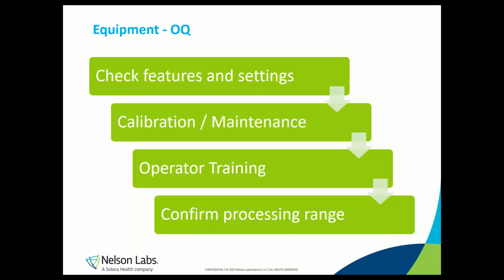The final key point is to determine the acceptable range of sealing for the specific package or the intended processing window. This is usually done by starting with a recommended setting and going up or down from there to see how that affects the seal. This is done either by performing peel testing on each setting to get the seal strength value or evaluating the visual appearance of the seal. You then pick a high, a nominal, and a low based on the seal strengths and or visual aesthetics. You can also just take the pouch manufacturer recommended sealing parameters and add a plus or minus of 2 to 5 degrees and create a processing window, and then test to verify that that window works.